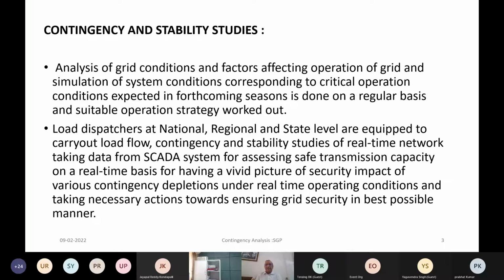So this is a regular feature in the national level load dispatch center, the regional load dispatch center, and the state level load dispatch center, where contingency analysis and stability studies are done on the real-time network. That is the most important thing. Normally you do the study based on the network parameters in an offline mode, but here you actually take the real-time values from the SCADA system and run the load flow program and the state estimation program to get a realistic picture of what the scenario is going to be if some contingency happens.